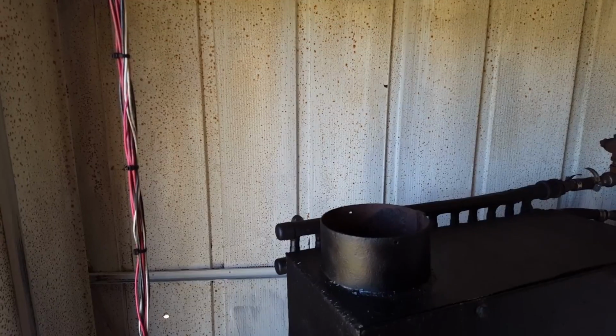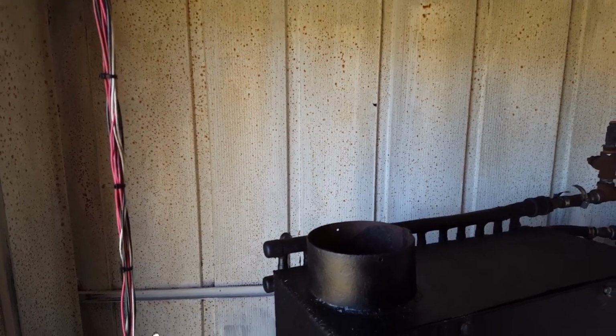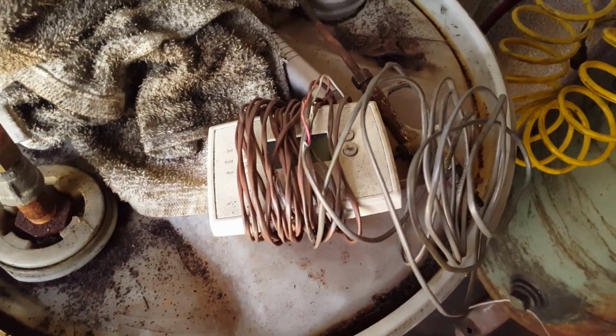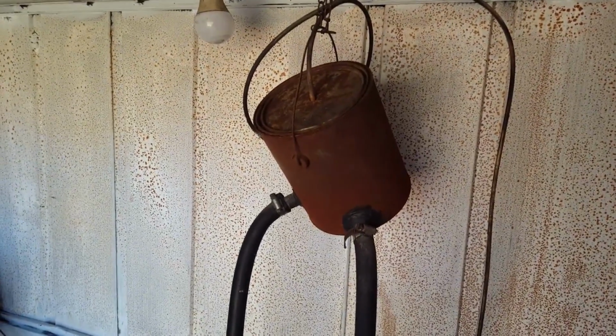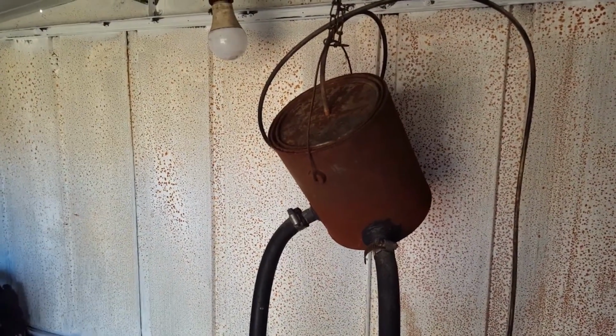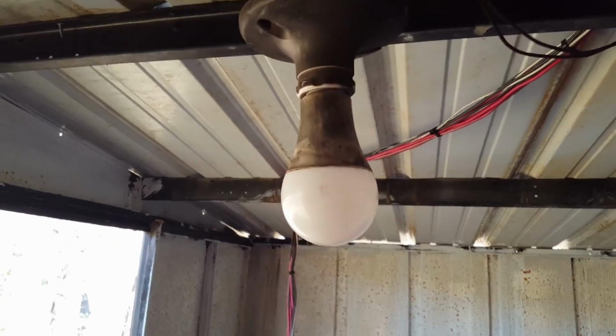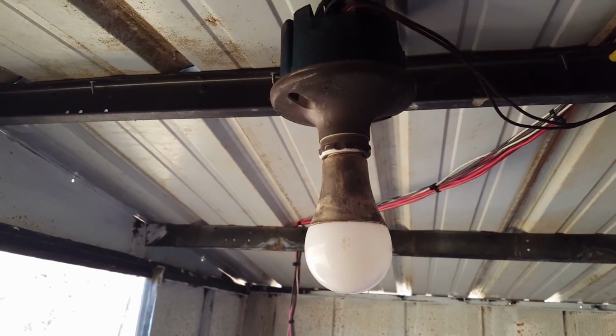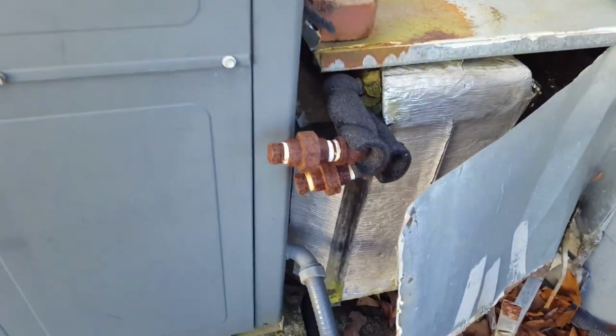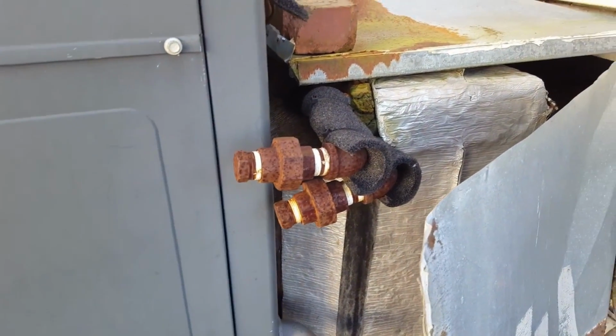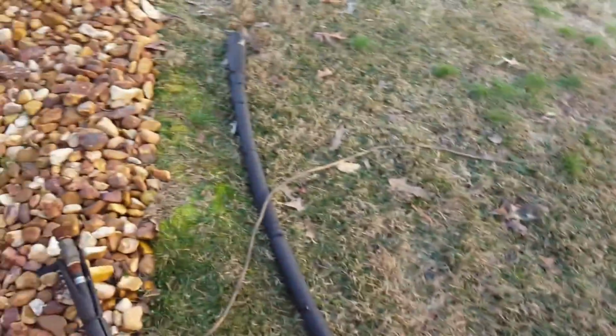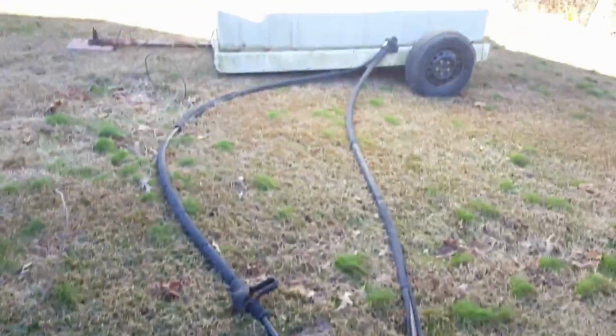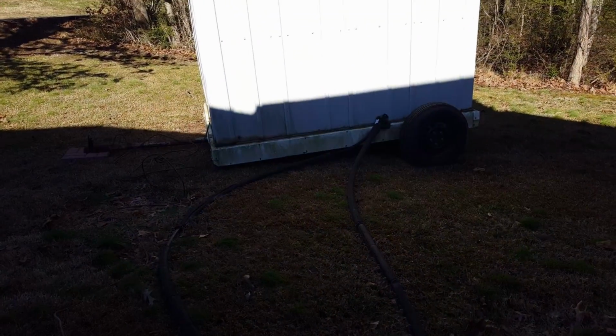I got a few more things I have to do, and I'm going to show you what I need to do. This is what's left before we can get this thing running. I have to cut a hole in that wall right there for the exhaust. I've got to run the thermostat wire into the house and get everything hooked up for it. We've got to fill it up with antifreeze, but before I do that, I have to hook the hoses up outside, and I'll show you that. And if I hit my head on that light one more time, I'm probably going to rip it down. Here's where I have to hook up the two lines for the indoor coil, and there's the hoses right there that I need to hook up. So let me get all that stuff done, and in an hour or two, we may be firing this thing up.